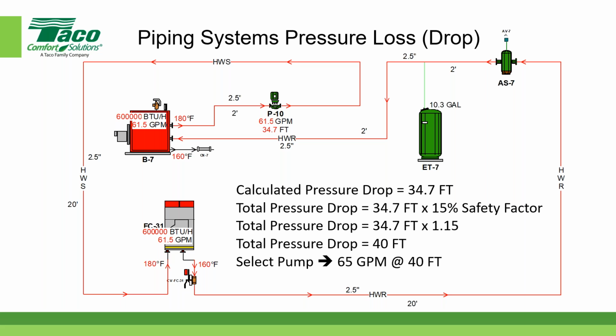So the pressure drop that we calculated manually was exactly the same pressure drop that the HS2 software calculated. And then we added a safety factor of 1.15, adding 15% to that, and that came out to approximately 40, not exactly, but we rounded it off. So let's do our math. 34.7 times 1.15 actually came out to 39.9, and I rounded it off to 40. And when I make a pump selection, I generally don't make the selection for the exact flow in gallons per minute. I usually add a little safety factor there. In this case, I added a safety factor and rounded it up to 65 gallons per minute. So if I'm making a pump selection to accommodate this little system, it would be 65 gallons per minute at 40 feet.